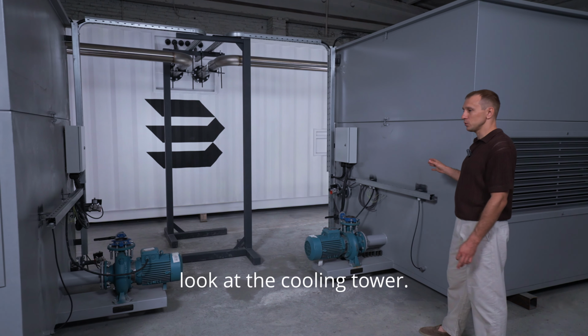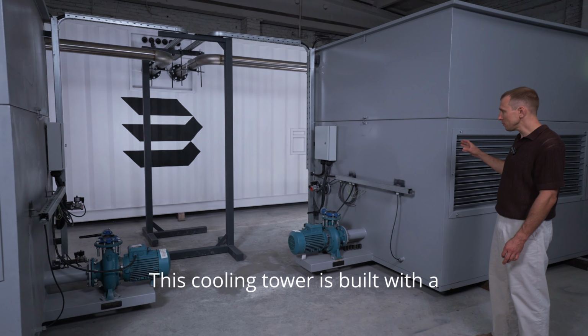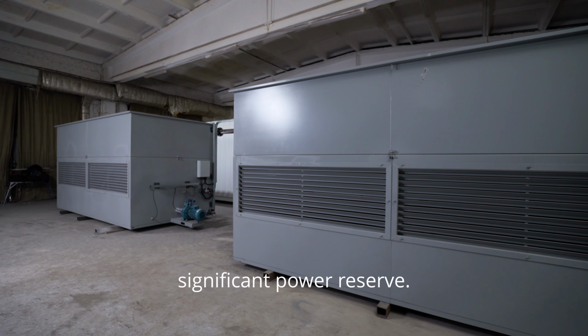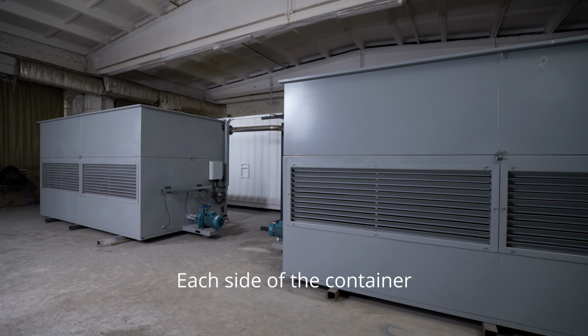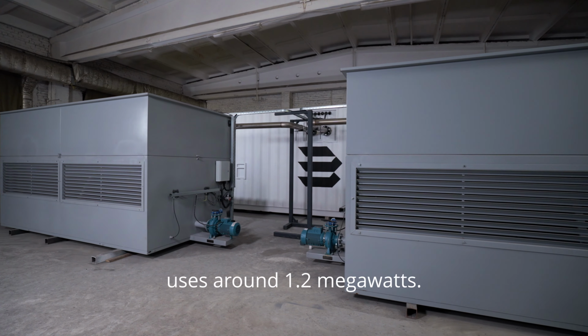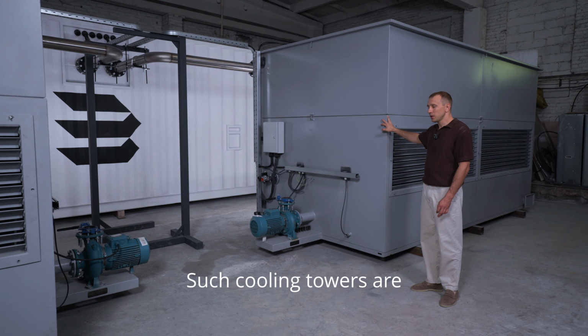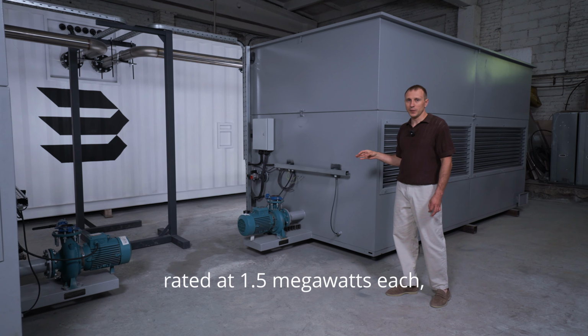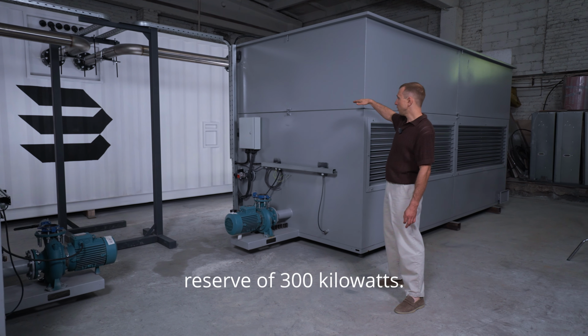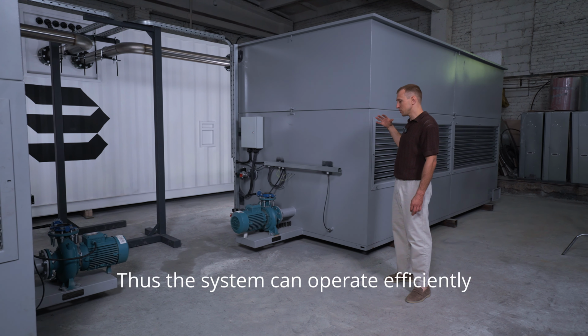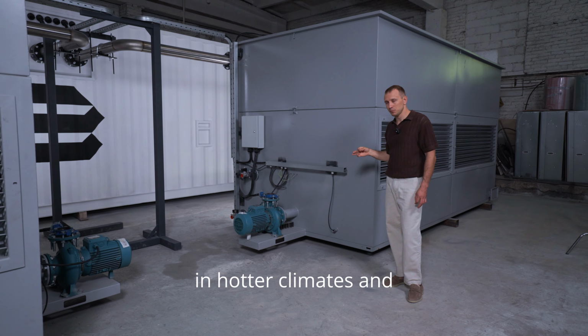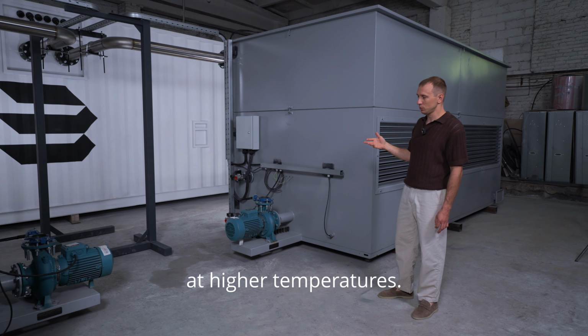Let's take a closer look at the cooling tower. This cooling tower is built with a significant power reserve. Each side of the container uses around 1.2 megawatts. Such cooling towers are rated at 1.5 megawatts each, which means we have a reserve of 300 kilowatts. Thus, the system can operate efficiently in hotter climates and at higher temperatures.